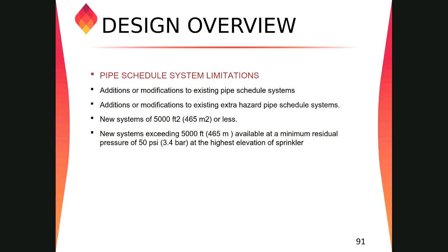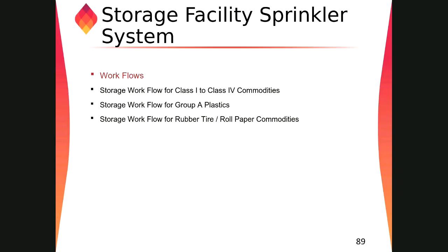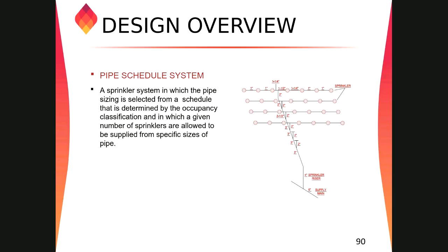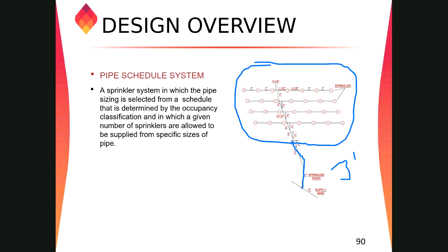So if the total number of sprinklers in your project is 60, we can use a 3 inch pipe from the riser. From the underground pipe, we take a tying point, put your riser valve and all the assemblies. So a main line, a riser, can supply water to 60 sprinklers.